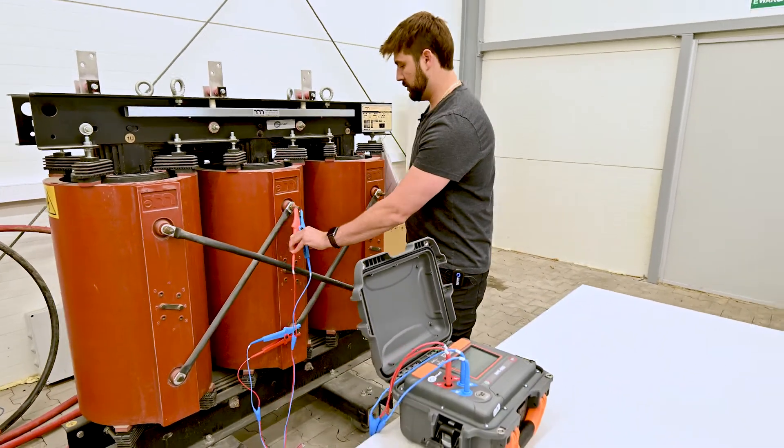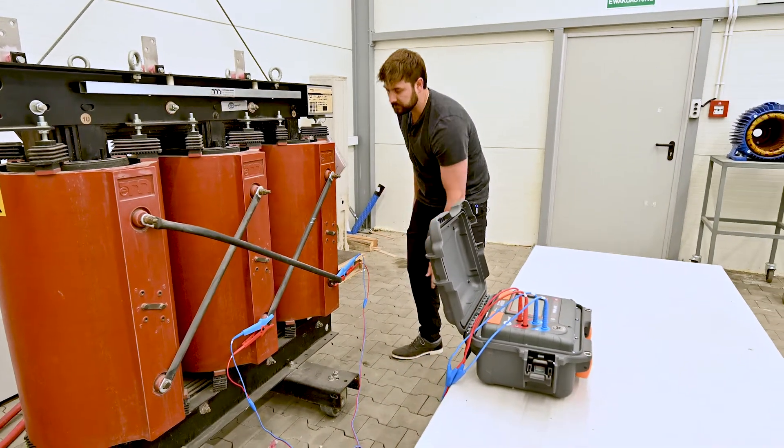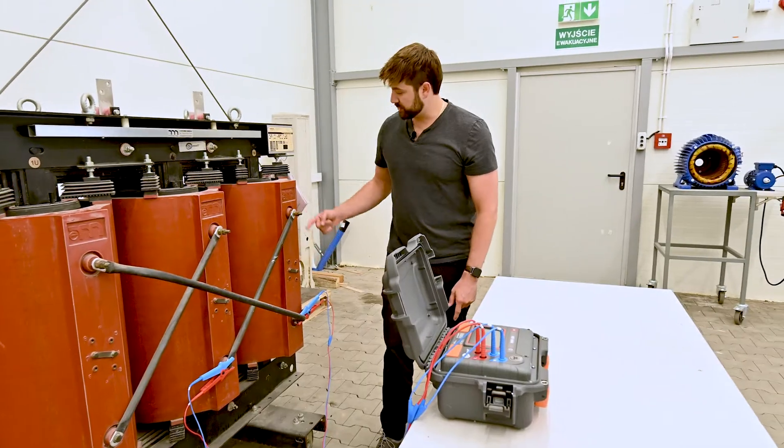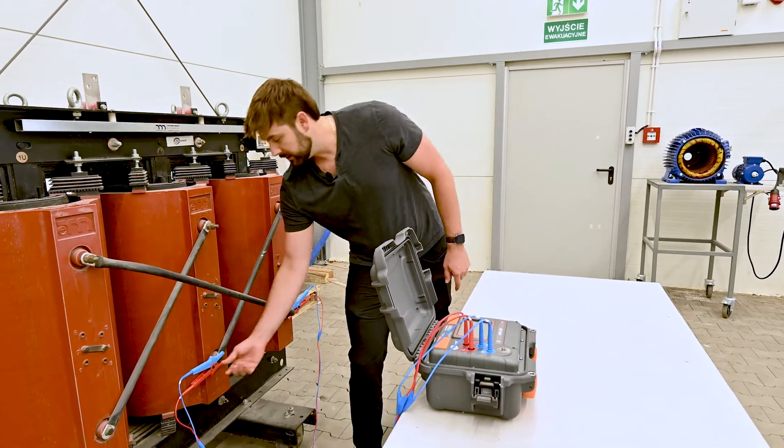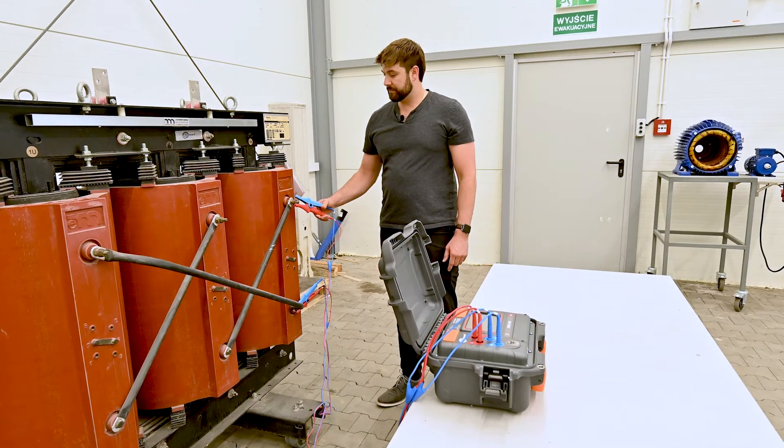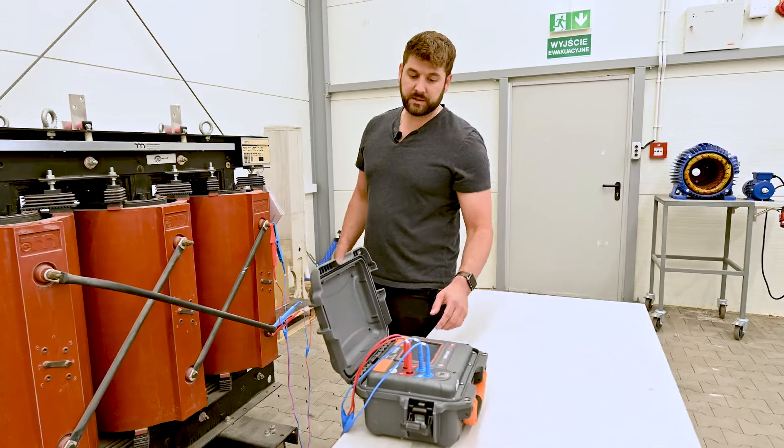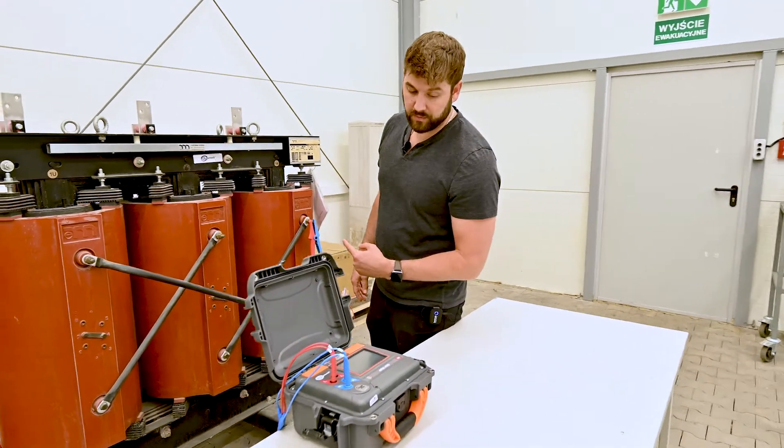Moving to the third phase, we can move this lead to here. Once again, I'm measuring across this winding. If I want to exclude this jumper, I can put my measurement lead here. Let's check the resistance of our third phase winding.